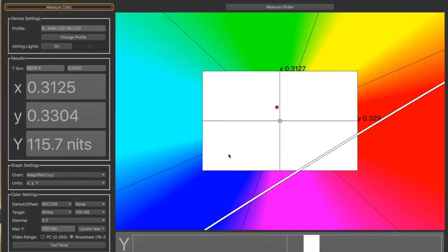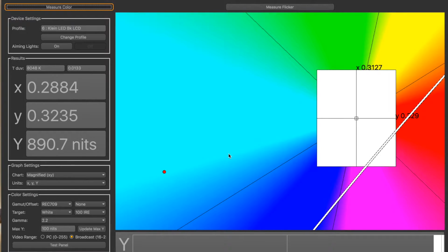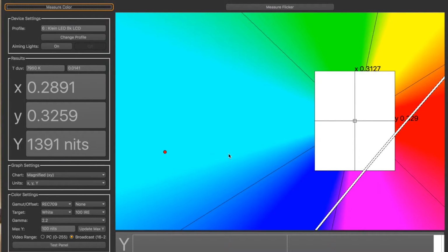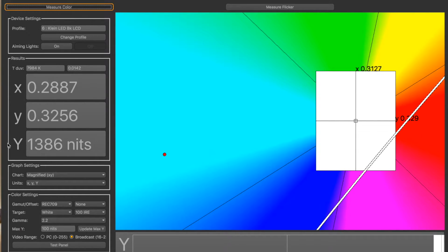But one of the features of this monitor is that it's an on-set monitor, and so it has a hi-brite mode, which if I go into the menus, and you'll notice that changes the colour, because obviously there's menus now in the way of the probe, and I go down to the max brightness option and I turn that on, you'll see how much this monitor brights up. So now the probe is just pointing at that same white field, but look at this, we're getting more than 1,000 candelas per metre squared off this little monitor.